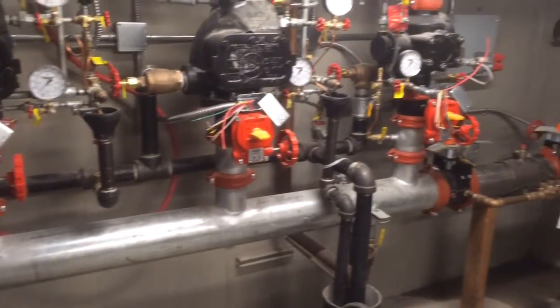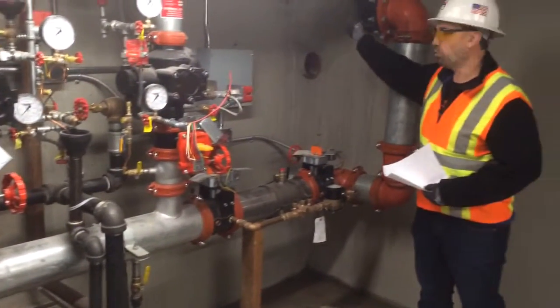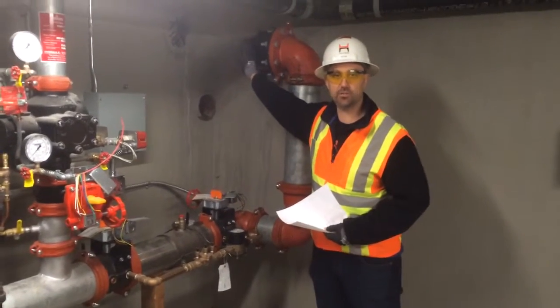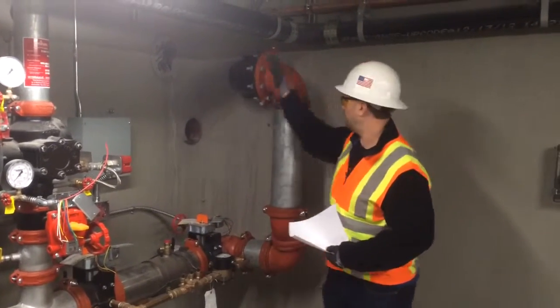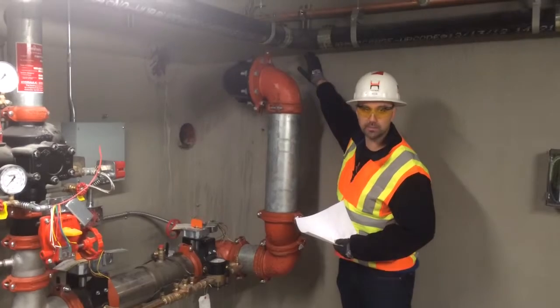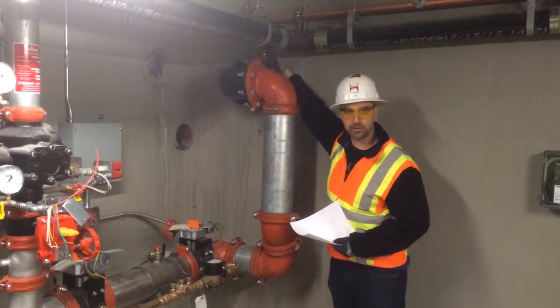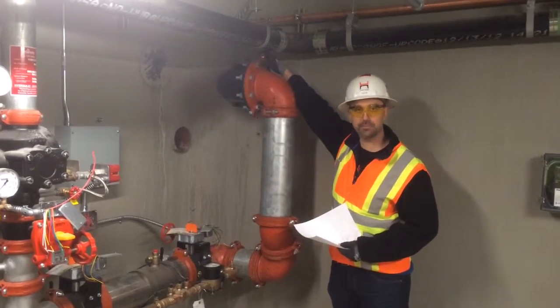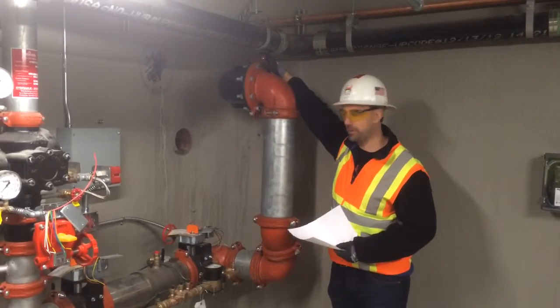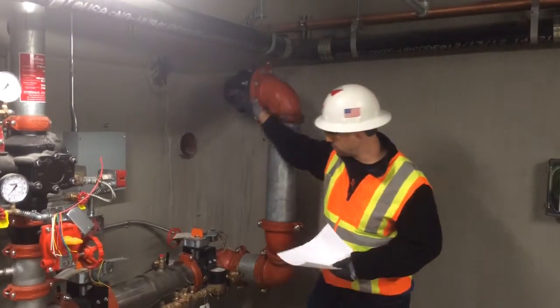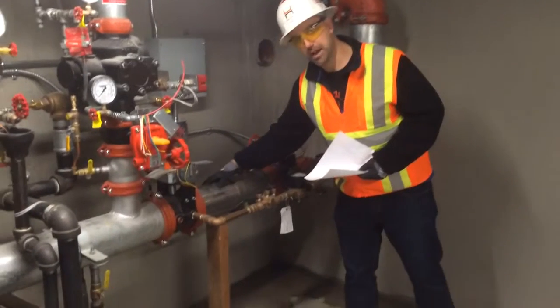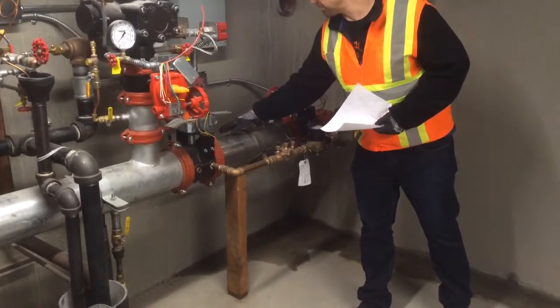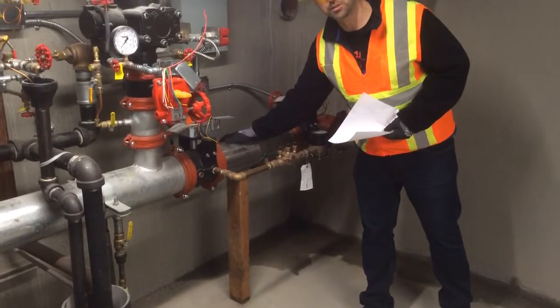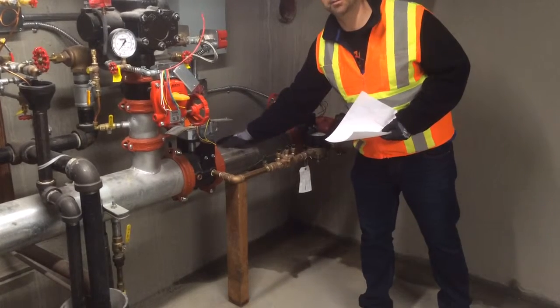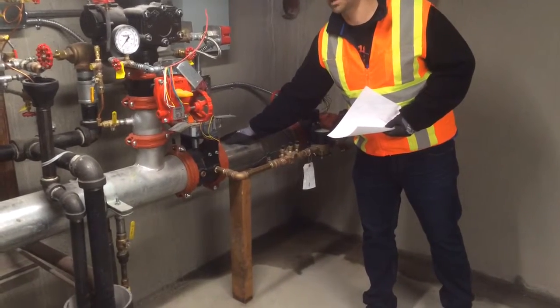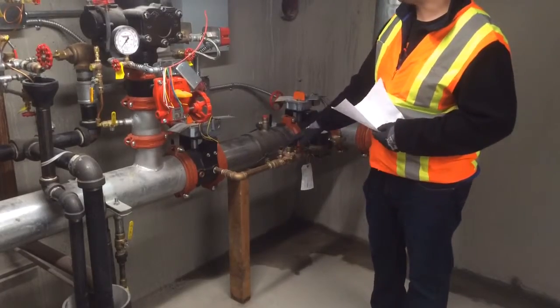The first one is civil coordination. We need to coordinate where the penetration of this water supply is into the building. On that side of the wall, it will be by the civil contractor, and on this side, it will be by the fire sprinkler contractor. We need to make sure they both understand where that pipe is. We need to coordinate on the civil drawings where this backflow preventer is going to be. Sometimes it's on the site and installed by the civil contractor, or sometimes it's inside the building installed by the fire sprinkler contractor.